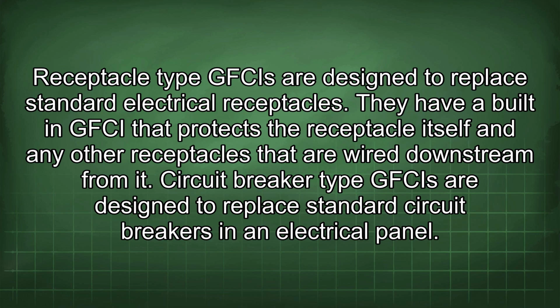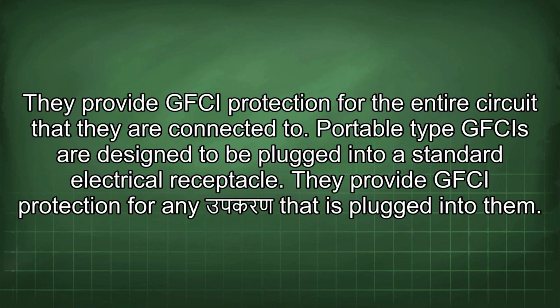Circuit breaker type GFCIs are designed to replace standard circuit breakers in an electrical panel. They provide GFCI protection for the entire circuit that they are connected to. Portable type GFCIs are designed to be plugged into a standard electrical receptacle. They provide GFCI protection for any appliance that is plugged into them.